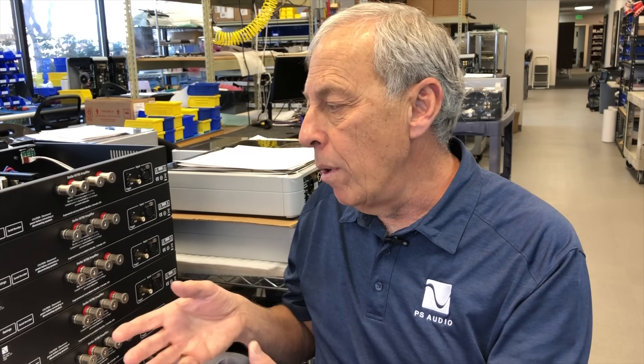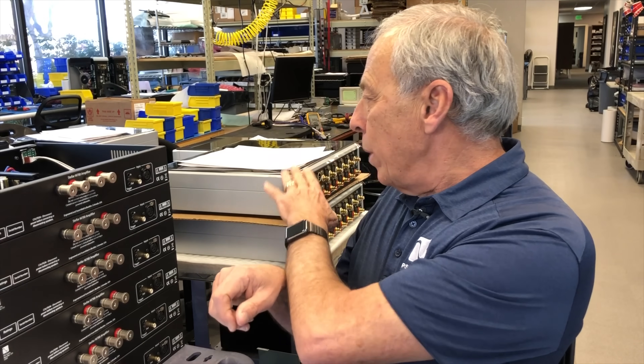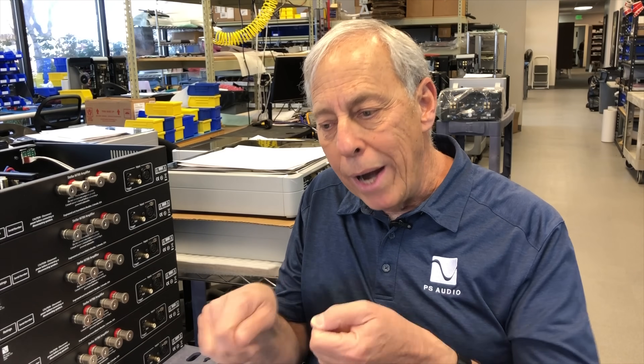So I have to change the primary so that the secondary gets what it wants — instead of a two-to-one reduction, it becomes roughly a four-to-one reduction for 220–240 volts. That requires rewiring the transformer if it has dual primaries, or sometimes replacing the entire transformer itself. Our transformers are all dual — actually triple — primary transformers because of Japan, so we can wire them differently. But it has to be done internally; it's not something you can just flip a switch and easily do.